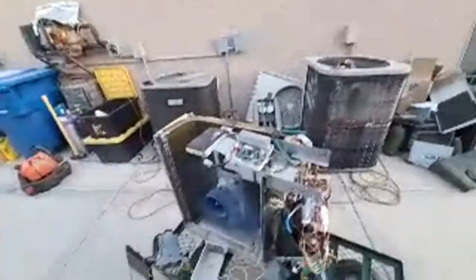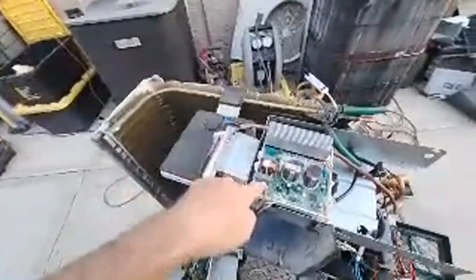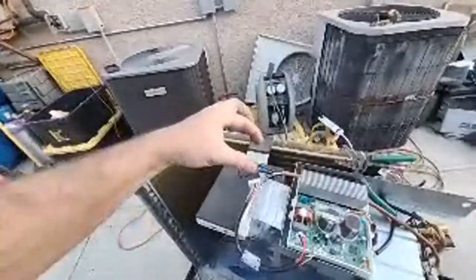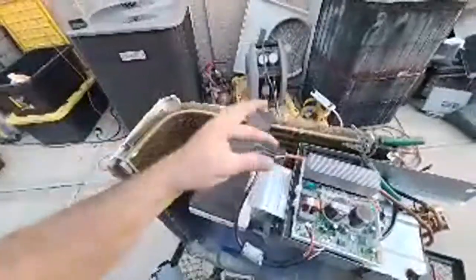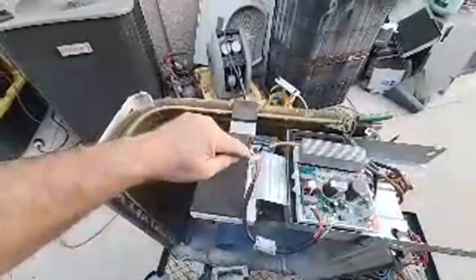So I need to make a new interface board that just connects to here to here. What my interface board did was pass the DC through a disconnect. I had loop connectors from the VFD's bus to my little circuit board, and then a 5-pin plug for this to plug in there. So it passed through the 330 volt DC to this, and then it just had 15 volt DC going through an optical isolator back to the inputs.